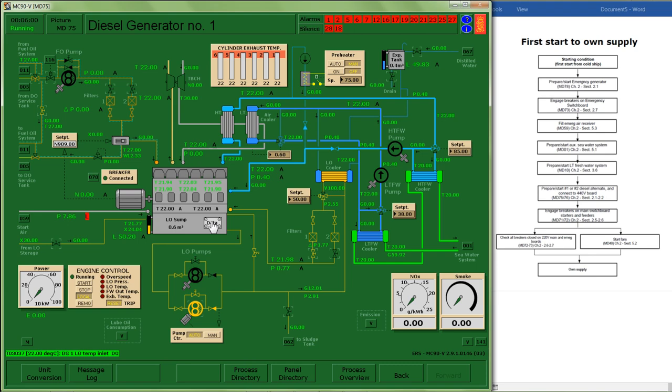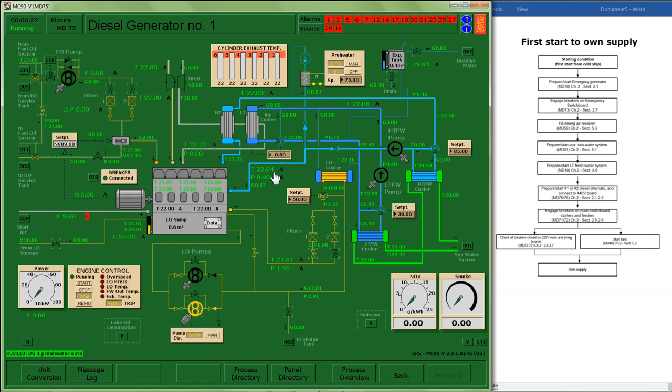I can confirm that my cooling water system has flow. So I have some flow going through that system. I'll turn on my preheater on my diesel generator so it's going to start to warm up some of the coolant. Normally you would want to make sure that this has completely warmed itself up. We may start it before we have met our normal operating condition.